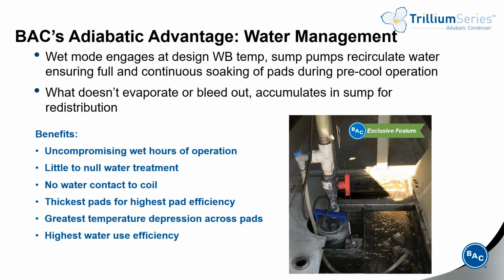What makes BAC's Trillium product different from other adiabatic products on the market? It's all centered around our water distribution system, the water sump, and the recirculating pump. In order to experience the benefits of adiabatic cooling, your unit needs to be running in wet mode. Otherwise, you have essentially just an air-cooled condenser. So we want to maximize the amount of time that the unit is able to run in wet mode. Recirculating and reusing the distributed water allows for more operational hours in wet mode.